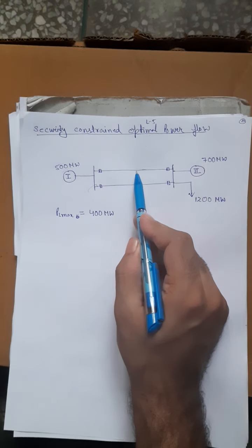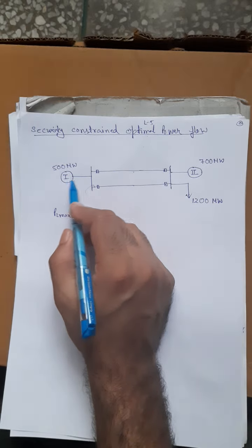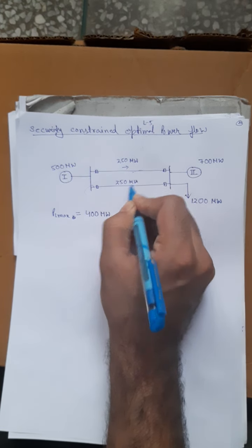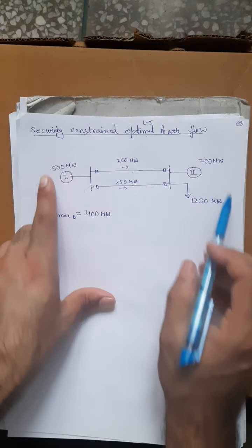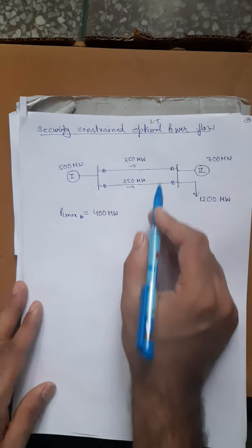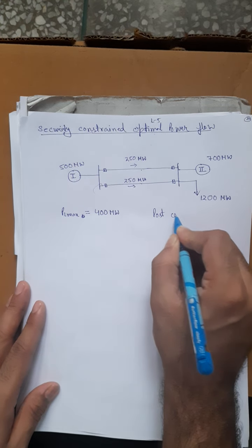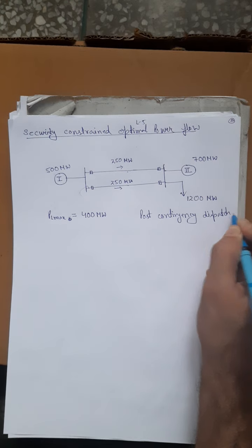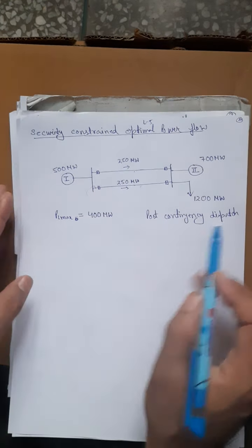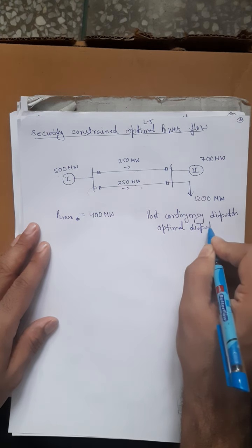Since the lines are parallel, power is equally distributed: 250 MW flows through each line. The maximum capacity is 400 MW per line, so at 250 MW each there is no problem. This is the optimal pre-contingency dispatch — the cost of generation is minimum.